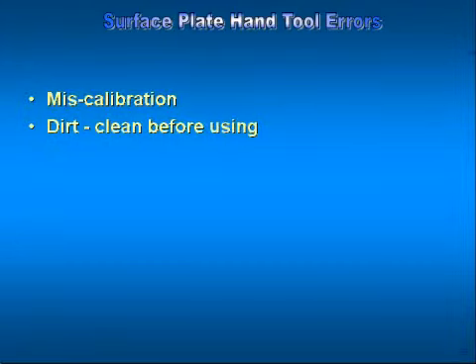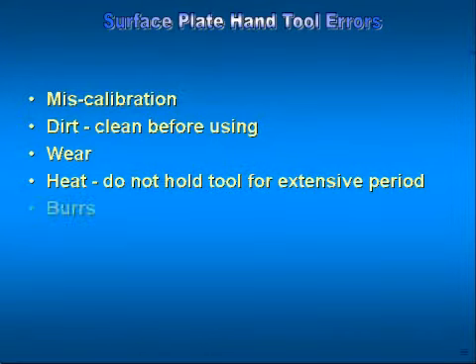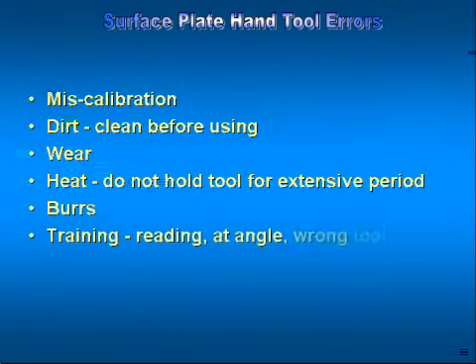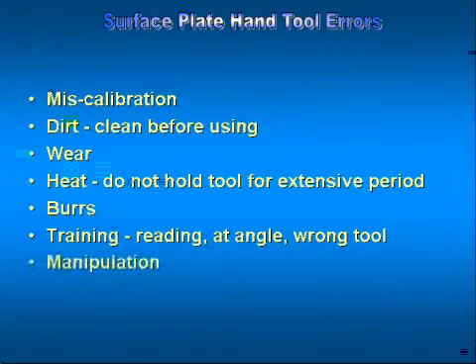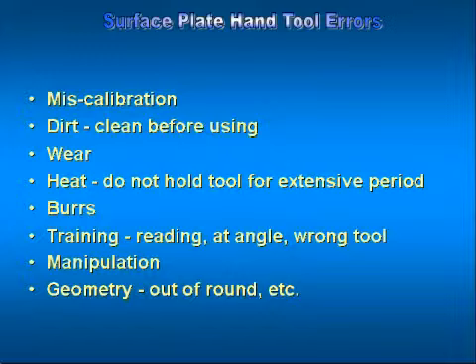Surface plate hand tool errors. There are several errors that can be made when using hand tools, such as the hand tool can be miscalibrated, it can be dirty, or it can be worn. Also, a tool can be held for an extensive period of time causing the tool to read incorrectly, and there can be burrs on the tools. Another problem that causes hand tool measurement errors is improper training, which can lead to the tool being misread or read at a wrong angle. There can be incorrect manipulation of the tool, and also a tool that is out of round.